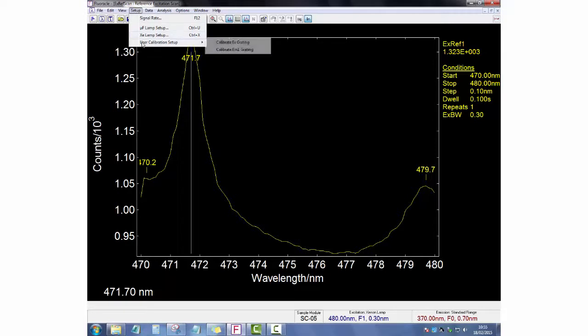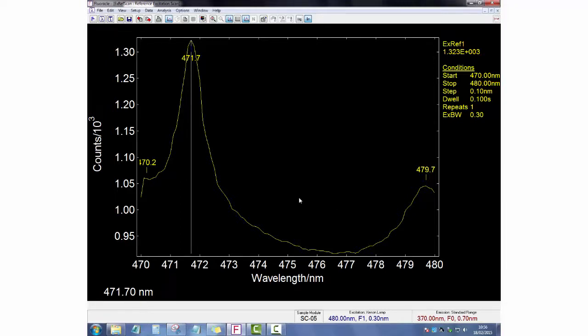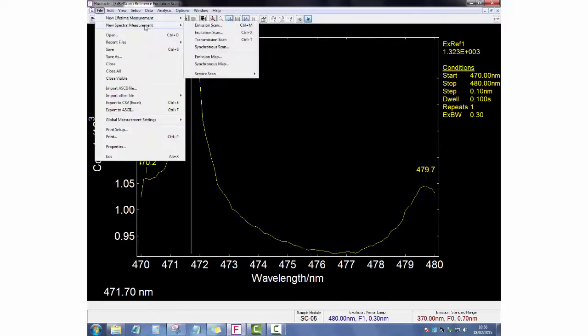If you measure the position of the line to be outside that specification, then go to Setup, User Calibration Setup, Calibrate Excitation Grating, and you input the value that you measure for the line position, for example 471.7 nanometers, and the desired value, which is 473.4 nanometers, and press Update.